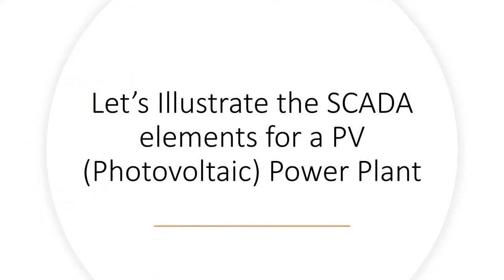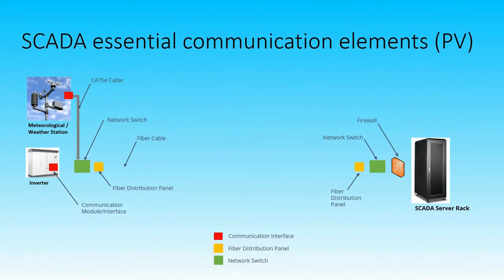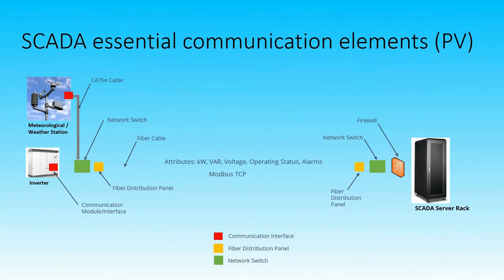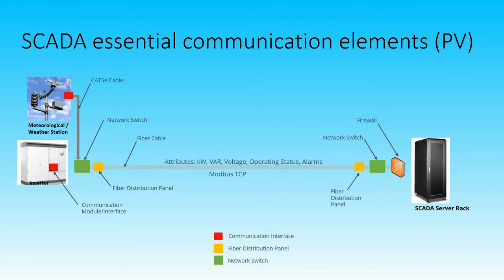Let's illustrate the SCADA elements for a photovoltaic power plant. In this basic diagram for a PV plant, attributes such as kilowatts, voltage, operating status, and alarms are being pulled from the inputs — like your inverters on the left. Those data sets are being transmitted to the SCADA server rack on the right through a fiber line via Modbus TCP. This also shows the essential communication elements like communication module interfaces as well as network switches.